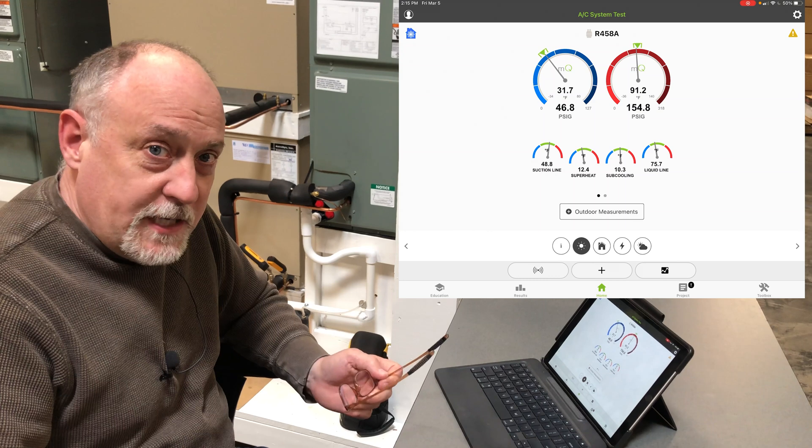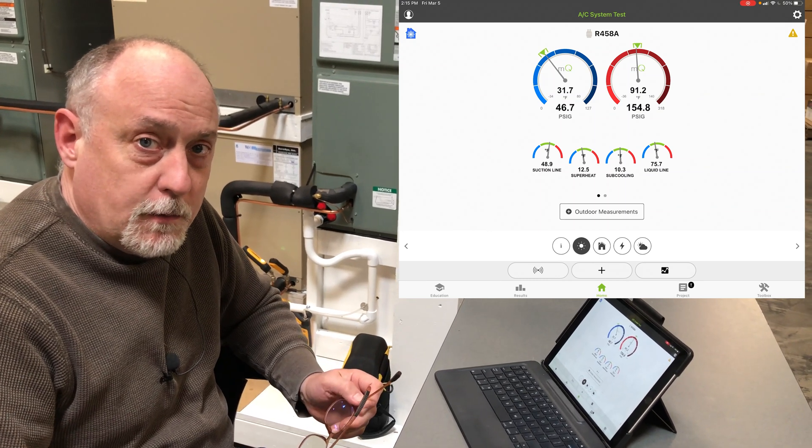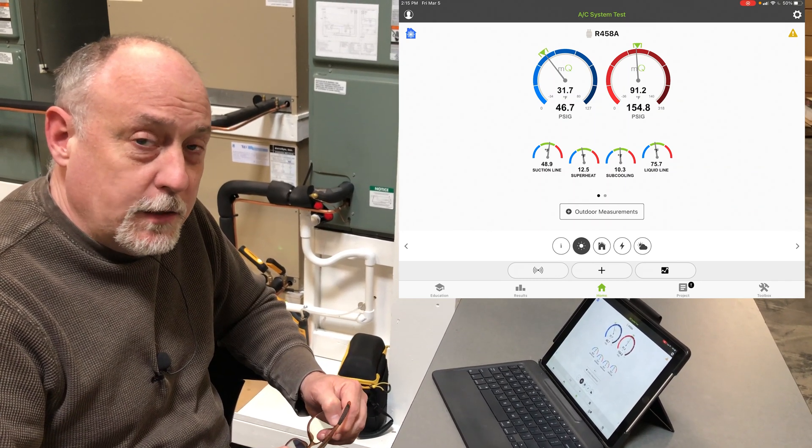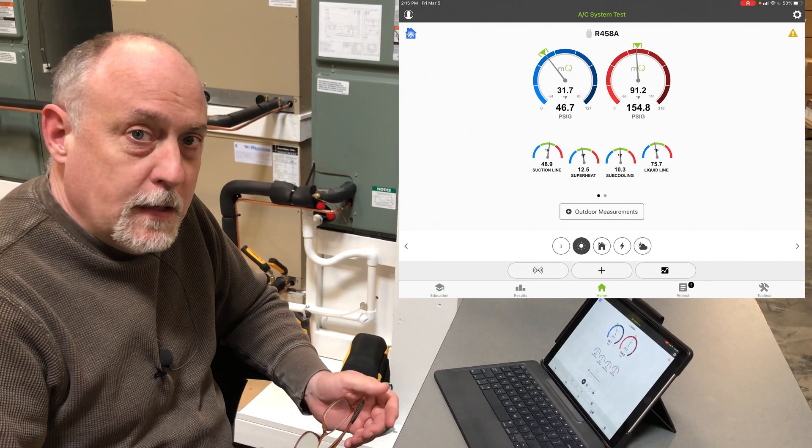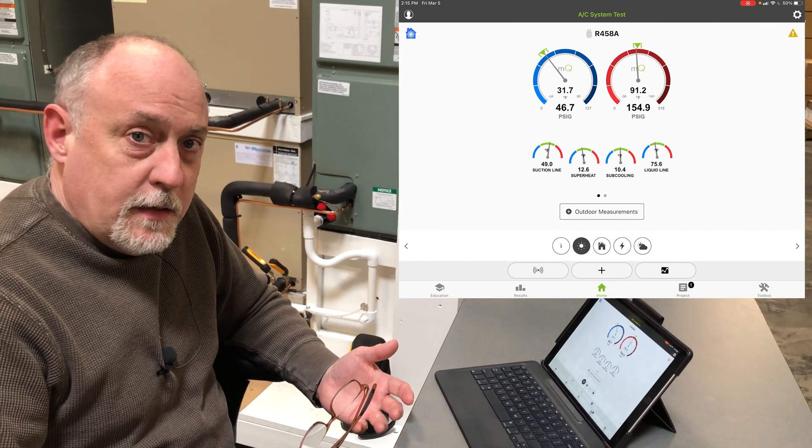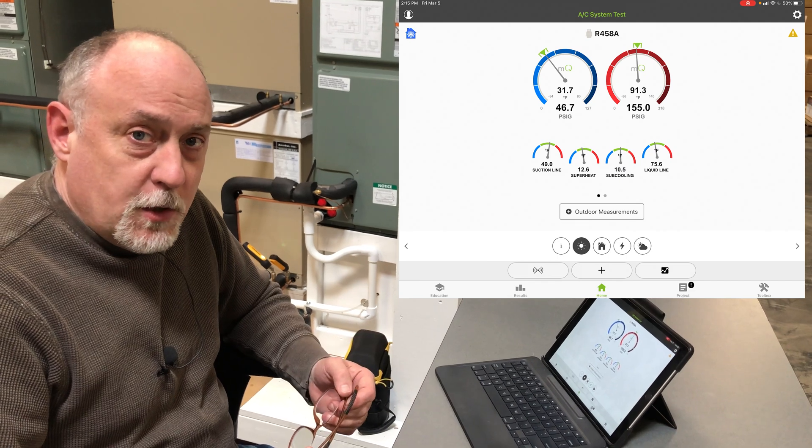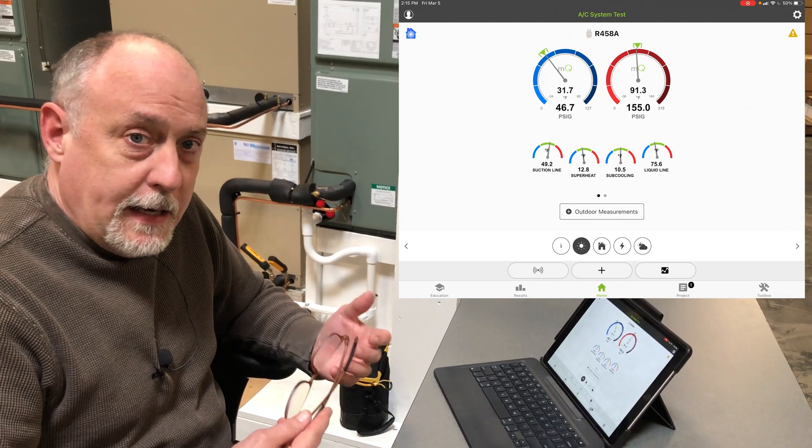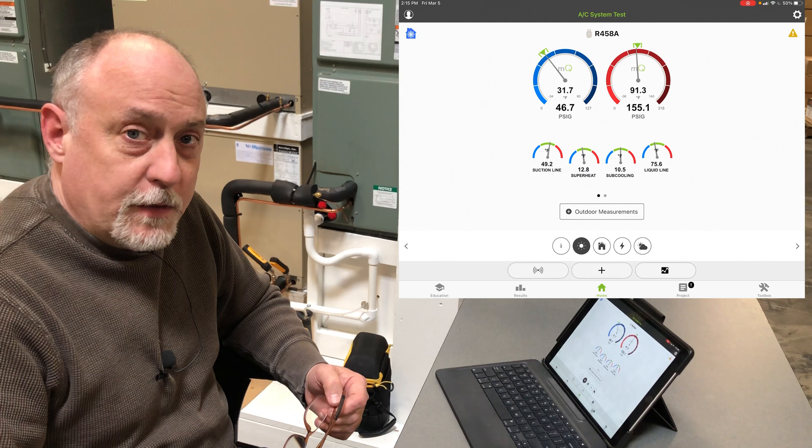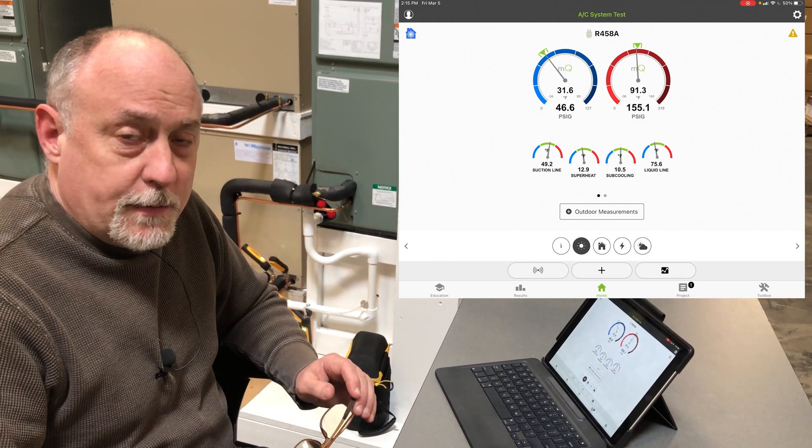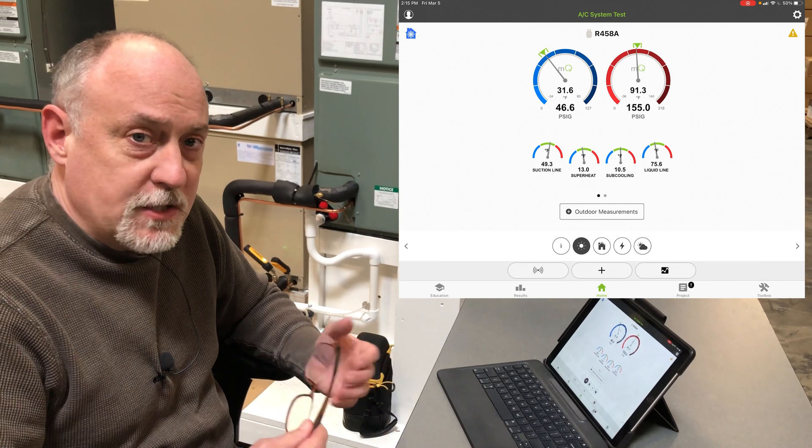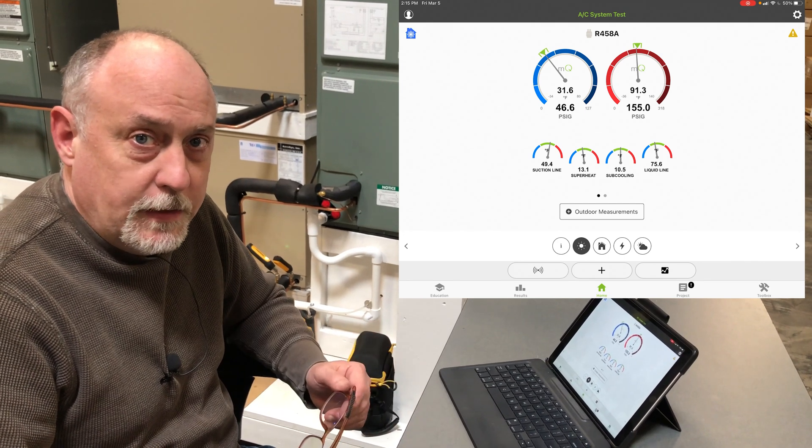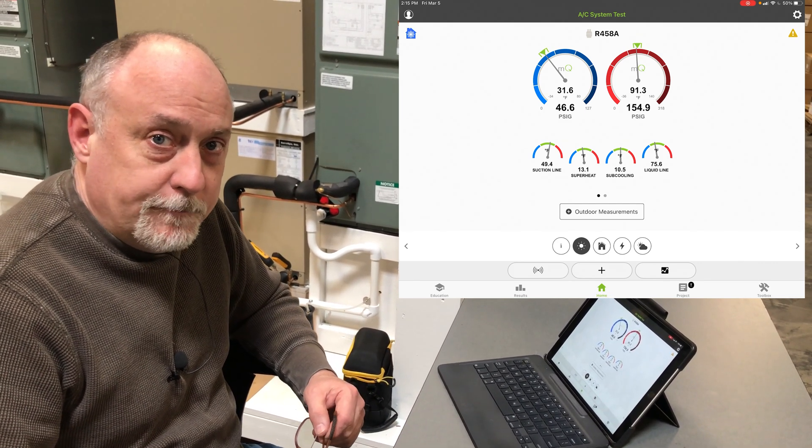Hopefully you've seen this and you understand that there's absolutely no reason we have to put gauges on a machine, because if I can calculate what my liquid line and suction line temperature should be, and they're within their allowable ranges, then the refrigerant charge is where it's supposed to be. The superheat and subcooling is where it's supposed to be, and the equipment will operate for years without losing refrigerant charge from connecting and disconnecting gauges every time or accidentally leaving a cap off. It's a sealed system. We want to keep it sealed. This is Jim Bergman for MeasureQuick. Thanks a lot for watching.